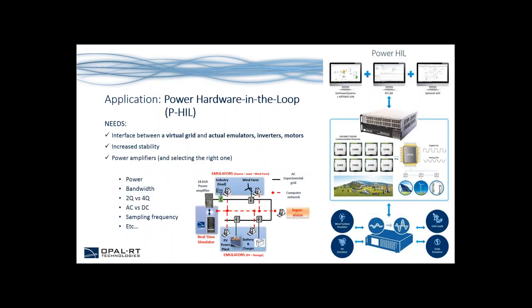One well-known application is Power Hardware-in-the-Loop (PHIL). For microgrids, this involves an interface between a virtual grid and actual emulators, inverters, and motors. We need increased stability due to the fact that power amplifiers are in the loop. One challenge is selecting the right power amplifier based on your needs — considering power, bandwidth, two-quadrant versus four-quadrant, AC versus DC, and sampling frequency. At Opal RT, we work with various third-party amplifier manufacturers to help you select the right one. The real-time simulator simulating the virtual grid interfaces with a power amplifier, which connects to wind turbine emulators, PV emulators, grid loads, motors, and inverters.